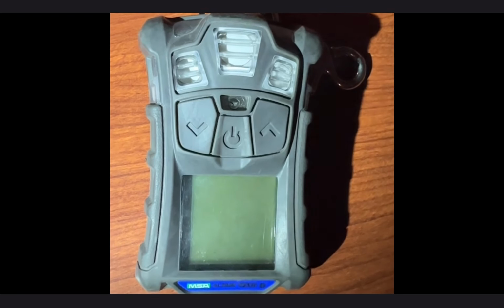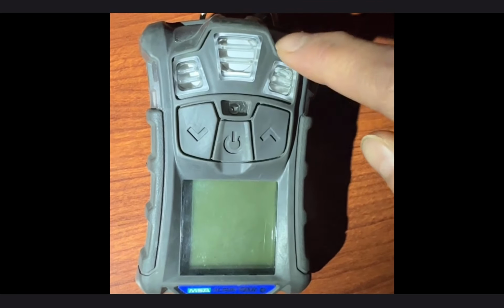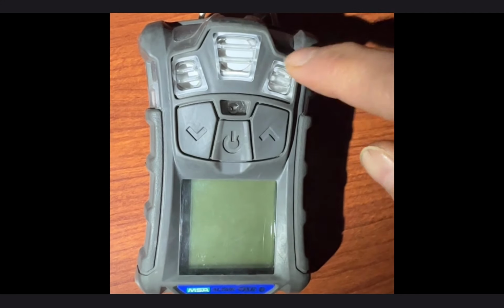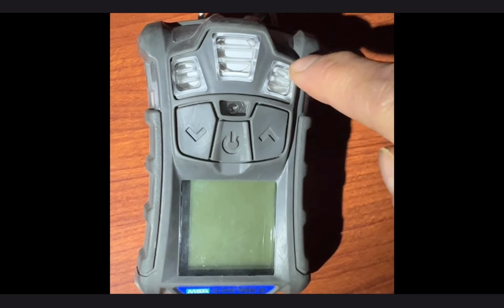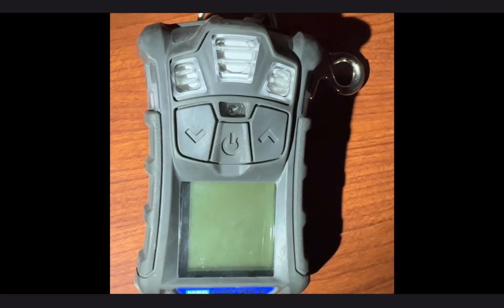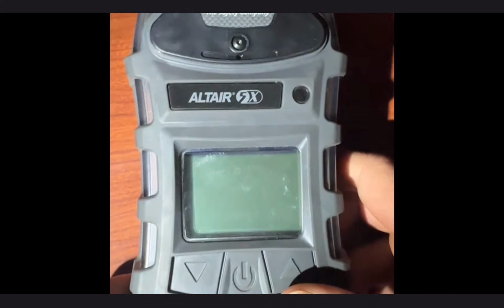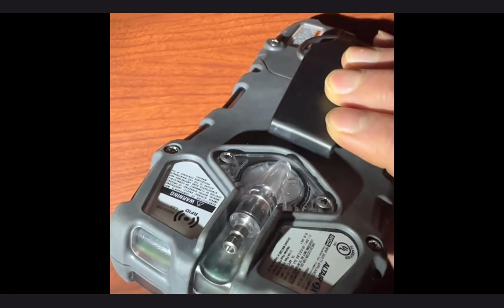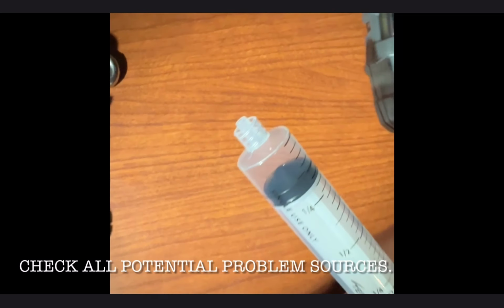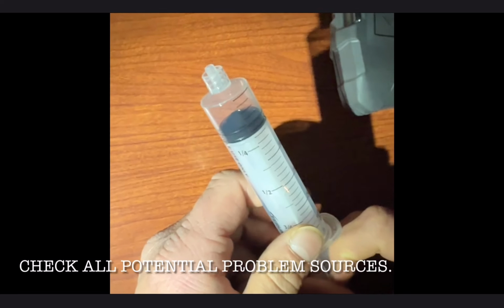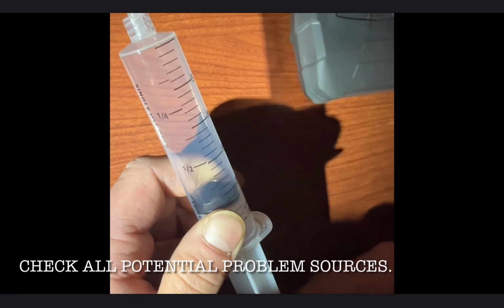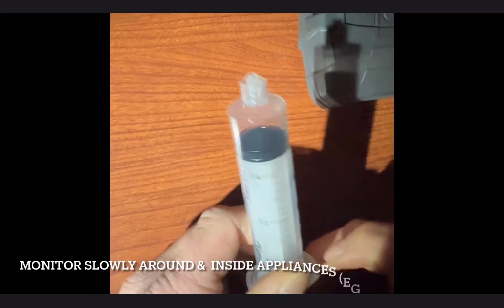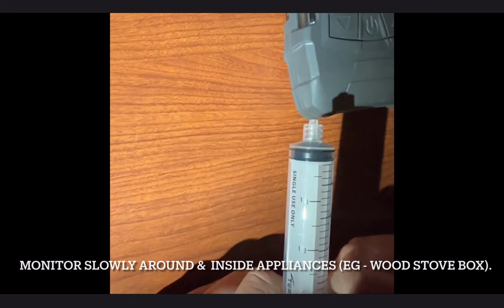The difference between the new monitors and these old ones is these ones are diffuse monitoring, meaning that you have to physically have these sensors in the product in order to get readings, versus the new 5X, which is a little bigger and has a pump built into it right here, and it'll actually draw in a sample. This is a 20 cc syringe. Think about drawing 3 syringe fulls of air; that's about how much you're pulling in through that pump every minute when you walk by.